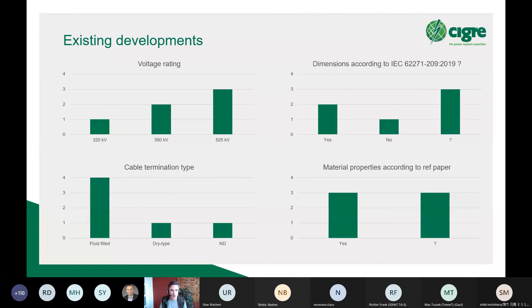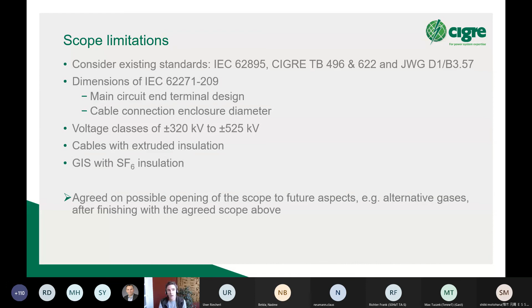So, like every good piece of work should start, we started with limiting our scope to bring a little bit of focus into our working group. So we will consider the existing standards, the CIGRE TB 496 and 622, and then the test requirements from the working group D1/B3.57. We will focus first on the cable connection assemblies that use the standardized dimensions from the IEC standard. We will consider voltage classes of 320 and 525 kV. We will only focus on cables with extruded insulation, kind of assuming that cables with mass impregnated insulation will not be used to be connected to an HVDC GIS. And we will focus for now on designs with SF6 insulation.